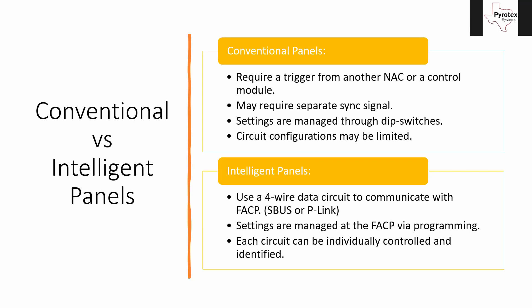Circuit configurations, depending on which panel it is, might be somewhat limited. Some panels might have two or three different inputs, and you can group the outputs by triggering different inputs. For example, a panel with four outputs and two inputs lets you group outputs one and two together, and three and four together, triggering those separately — or set it up where all four trigger together.